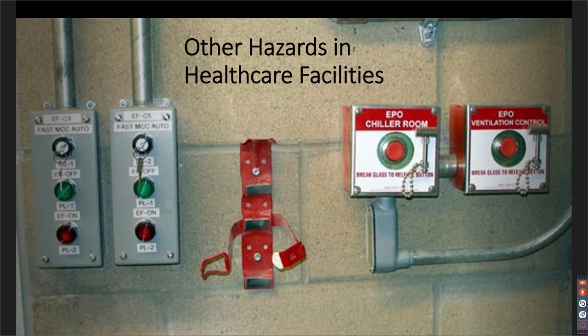Most of these refrigerant machinery rooms require some form of a purge system, so I might have to have an automated fan system completely capable of exhausting and purging the room, as well as emergency power off buttons located outside of the room to kill power for fire department use and entry.